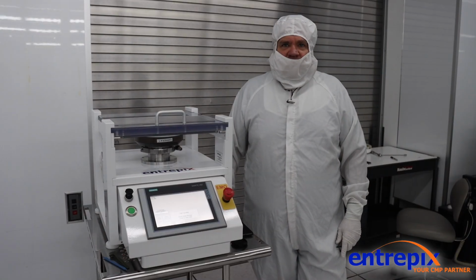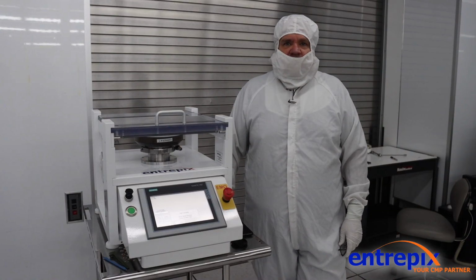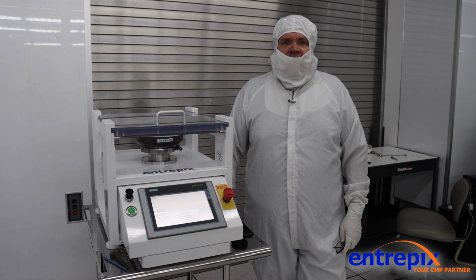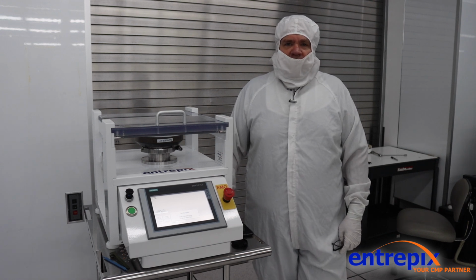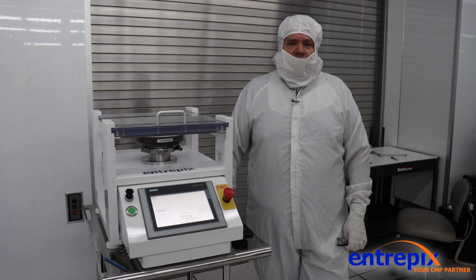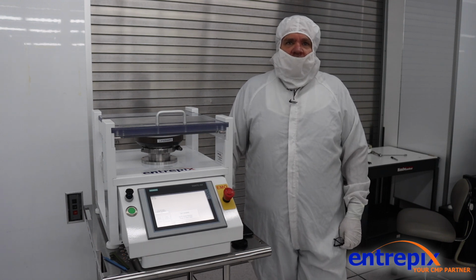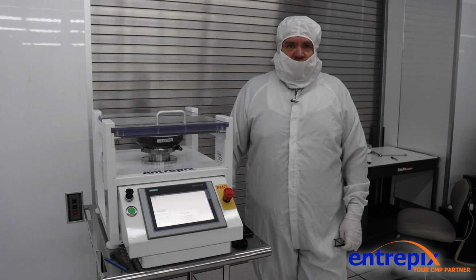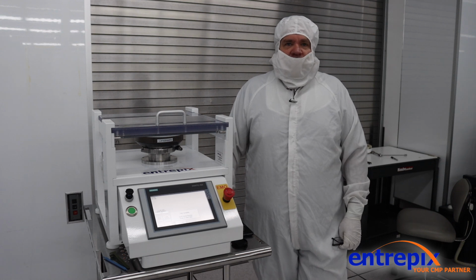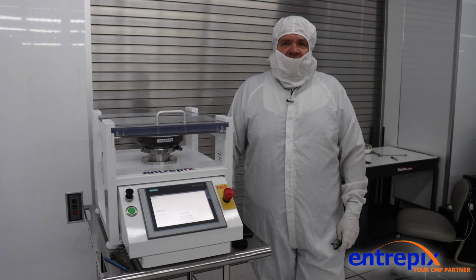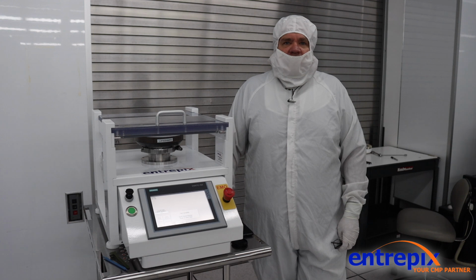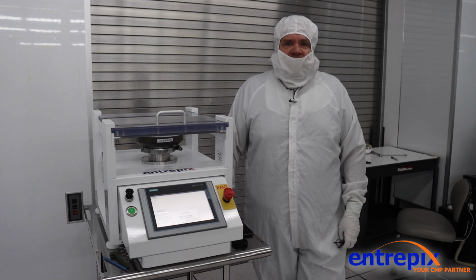As you have seen, the Entrepix head tester has a lot of testing and troubleshooting capability, allowing the operator to see all the pneumatic functions in real time, which enables greater troubleshooting ability. The manual operation empowers the service personnel to efficiently drill down within each zone of the head and truly find the root cause of failure. Having these highly customizable parameter settings allows testing at various zone pressures that can be matched to the actual production process recipe.